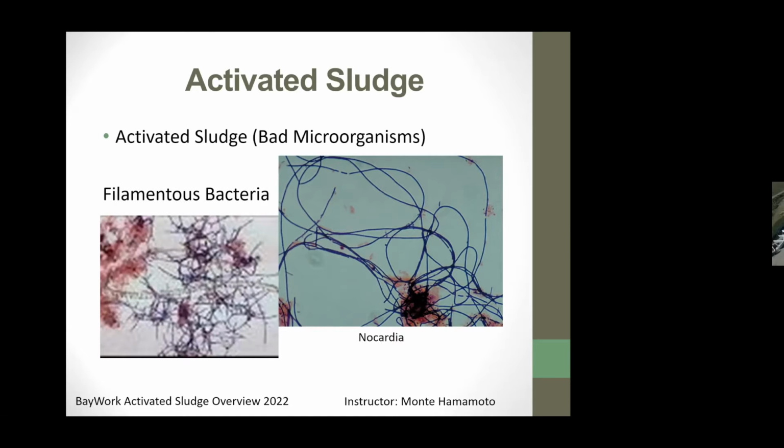It's a good question, and it's kind of difficult to answer because it all depends on where you're at in your activated sludge process. If you're having low inventories, let's say your mixed liquor suspended solids is around 1,000, you don't have a lot of inventory and it's kind of on the thin side and you're young already, if you hit it with a heavy dose of chlorine, you're going to do some damage. But if you're in the longer end and you're in the higher MCRTs and SRTs, you're going to have more microorganisms there, and you can increase that RAS a little more. Most likely you're going to be in that longer, older sludge when the filaments start showing up.